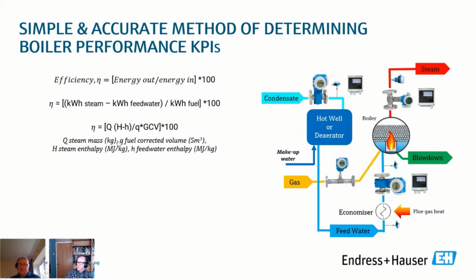This next one is what a lot of people do when they ignore the flow meter here. So what they're doing is assuming really that there's no blowdown, and they're assuming what goes in comes out, just to get an easy way of calculating the efficiency, but without using as many instruments. You'll be a couple of percent out in the calculation, but this way we're looking at the steam mass, and the mass they're assuming is the same mass throughout the system.